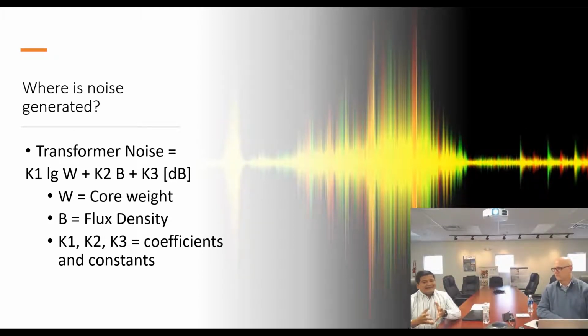But in order to mitigate the transformer noise, it is essential to know the amount of noise generated inside the transformer. With the wide range of transformers that we have designed and the number of transformers we have tested for the noise level at VDC and GTC, we have developed an empirical formula to estimate the sound generated by the transformer during its operation. So this is a design stage transformer noise calculation that we do to identify the exact amount of noise generated by a transformer. The transformer noise equation, as given here, is K1 log W + K2 B + K3. In this, W stands for the core weight, B is the flux density, and K1, K2, K3 are the empirical calculated factors that we use to calculate the transformer noise. So in simple terms, the transformer noise is a function of the core weight and the flux density applied for that transformer.